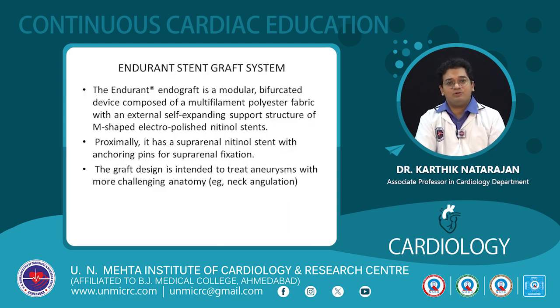The Medtronic has the Endurant stent graft system. It's a modular bifurcated device composed of a multifilament polyester fabric with a self-expanding support structure of M-shaped electropolished nitinol stents, and proximally it has a suprarenal nitinol stent with anchoring pins for suprarenal fixation. The graft design is intended to treat aneurysms with more challenging anatomy. The Medtronic company claims that the Endurant can be used with an aortic neck length of around 10 millimeters. Just at 10 millimeters you can have a good fixation if you place the stent below the renals.